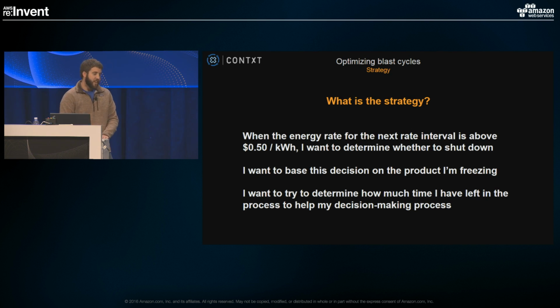So in this case, kWh is billed like if you have a gallon of water, you're saying every gallon of water I want to charge this rate. During the day, that changes 24 times. Every hour of the day has a different rate schedule. And if it was really hot in downtown LA the day before, then it's going to skyrocket. Typically, in North Carolina at least, you pay about 10 cents per kWh. To put this into perspective, certain days of the year in Oxnard, California, it costs about $4 per kWh, which is absolutely insane. So we want to take that into account.